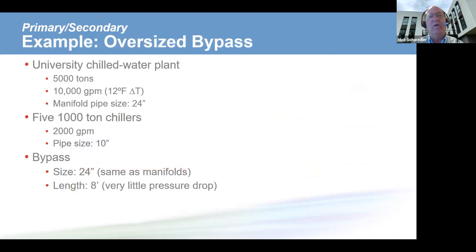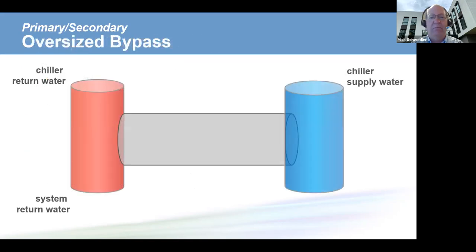Now, there are some issues if the bypass line is missized. And frankly, we see this on large chilled water plants quite often, and it can cause some problems. So we'll talk about what the issue is, the problems, and then what you could possibly do to take care of this.